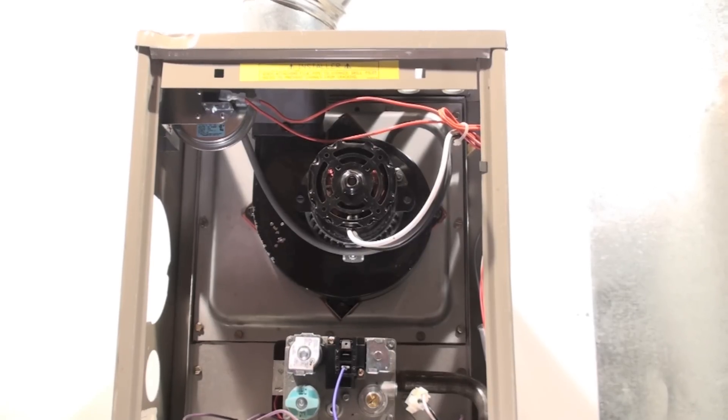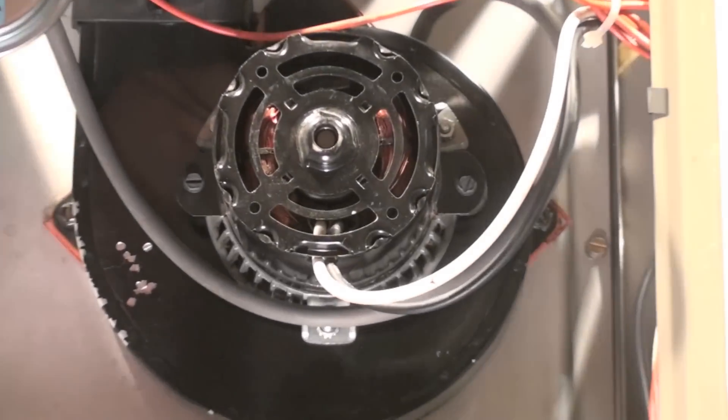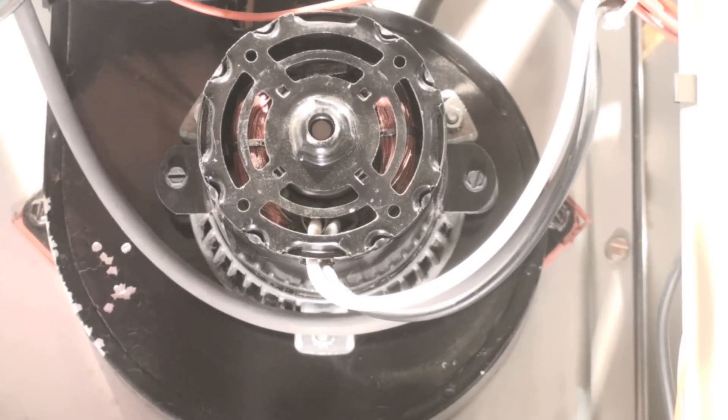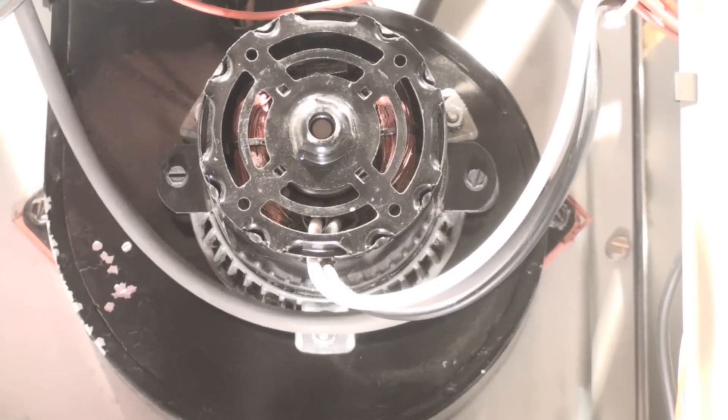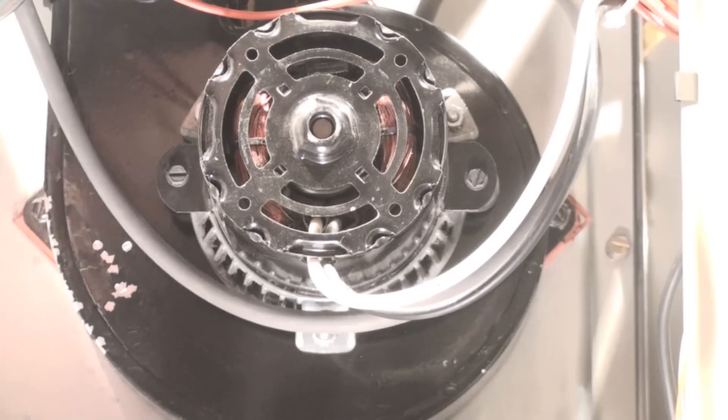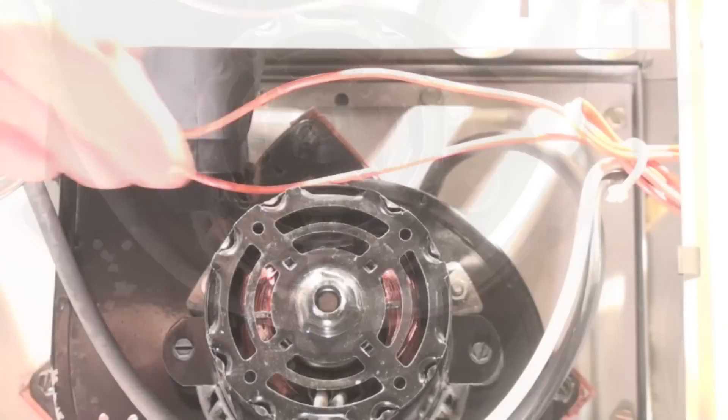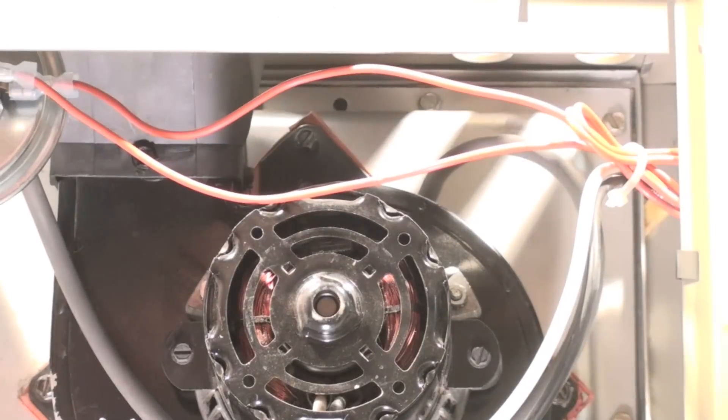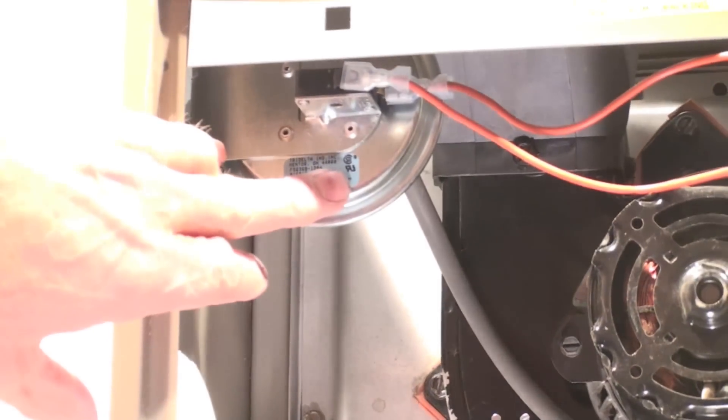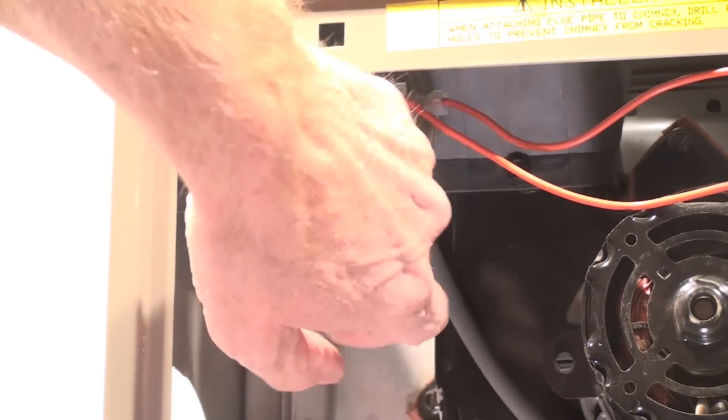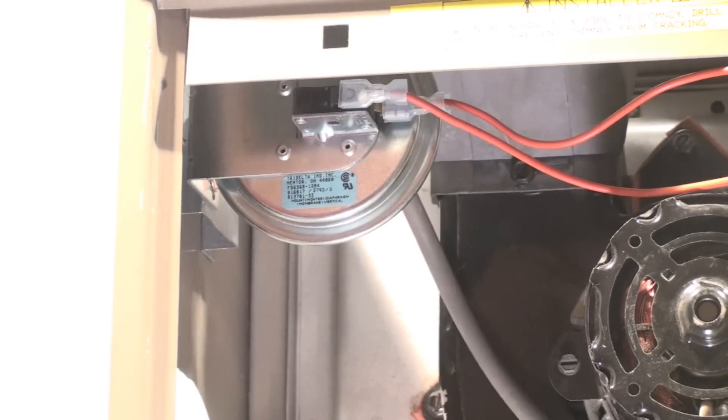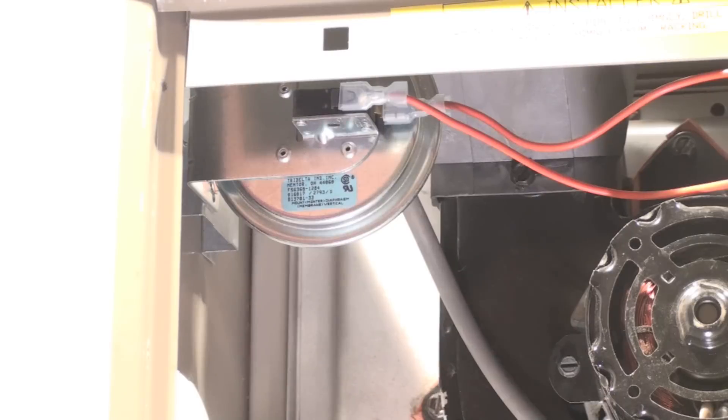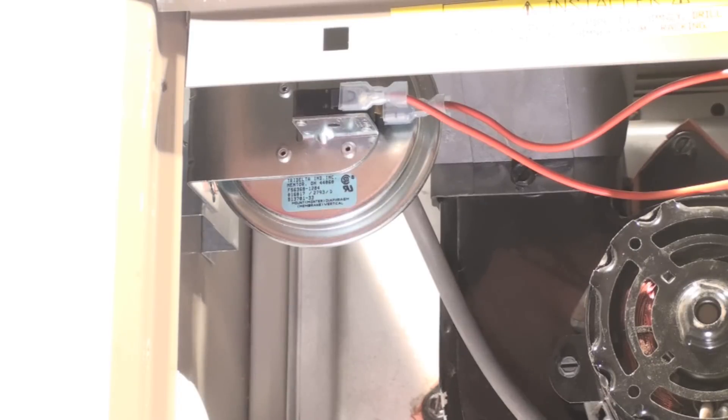What it's going to do is prove that it's on through this tube here. This tube comes right off of here, comes around over to the pressure switch, hooks on to the back of the pressure switch. It has to pull a certain amount of vacuum or nothing happens—it won't go any farther. Let's recap that a little bit.